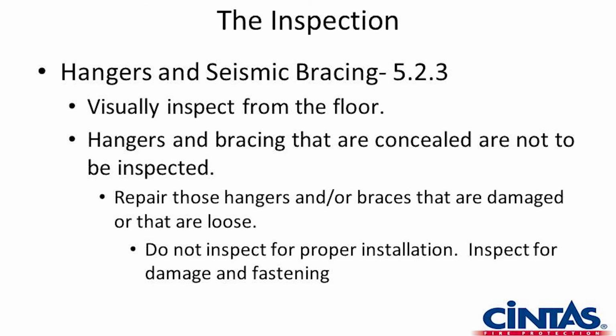Hangers and bracing, we're looking just to make sure that, if a hanger has vibrated loose from the beam clamp that is attached to the structure, the rod will cause it to swing around. So you'll have a hanger on the pipe and a straight rod sticking down. That's a very obvious sign that the sprinkler pipe hanger has a deficiency, needs to be reattached, or find out what caused it to fall away. The seismic bracing, we're looking for that to make sure that those are in place and tight. Last thing, we do not inspect for proper installation, we inspect for damage and fastening.